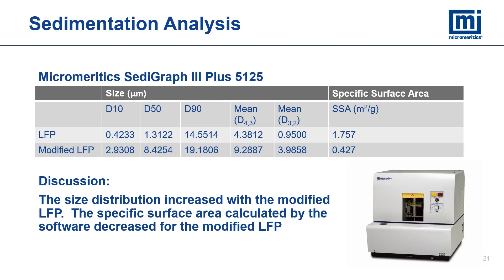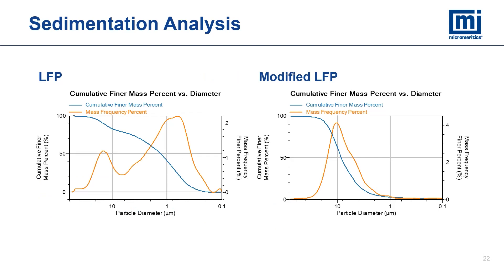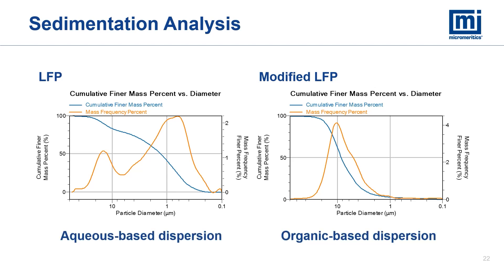You can see the difference in the D50 and D10 values — there's a dramatic difference between those values. You can also see it in the mean D43 value, which is the mass-weighted mean diameter. Also reported here is the D32 value, which is the surface area-weighted mean diameter, as well as the specific surface area calculated from the particle size distribution. Looking at the size frequency plot, we can see that the LFP is bimodal and the modified LFP has only one mode. The single mode of the modified LFP seems to match the coarser mode of the LFP distribution around 10 microns. It is important to note that the LFP was dispersed in water with surfactants and the modified LFP was dispersed in an organic liquid with surfactants since it is hydrophobic.